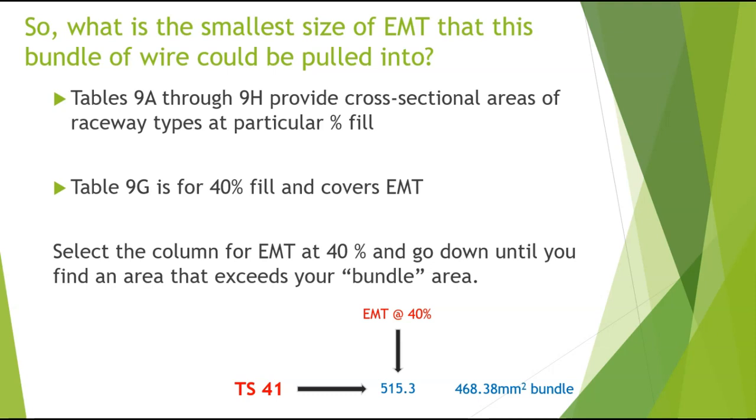And again, if we're pulling anything more than 2 conductors or cables through a raceway, we are required to go to a maximum of 40% pipe fill.